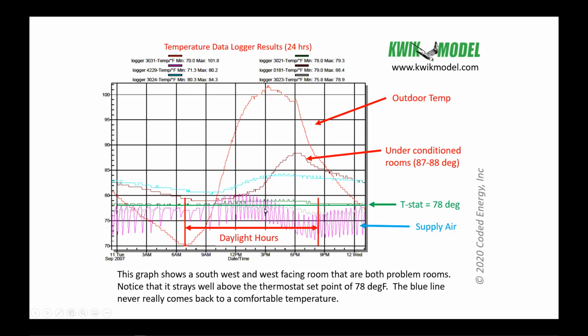If this was properly sized equipment, when it went above 78 degrees, this pink line should drop down and stay down and run continuously until it cools off and then come back up. And what you'll find is that you don't have these peaks. What happens is these rooms start to stray away, and every time the air conditioner shuts off, it rises a little bit, it runs for a little bit, and it ratchets up and ratchets up and ratchets up. That is a classic example of what you get when you short cycle.